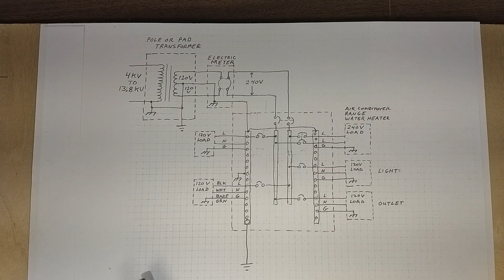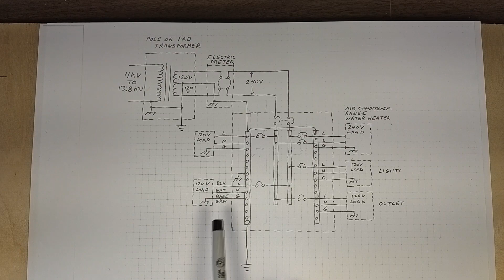This diagram represents a typical electrical system in a house or a building, and it's just to show things in general and not be highly specific. Generally, somewhere there will be a transformer either mounted on a pole or a pad, or in some cases even underground, and it'll be fed by relatively high voltage. This voltage depends on how far you are from your nearest substation. The secondary of that transformer is actually 240 volt center tapped, where the center tap will run to earth ground.